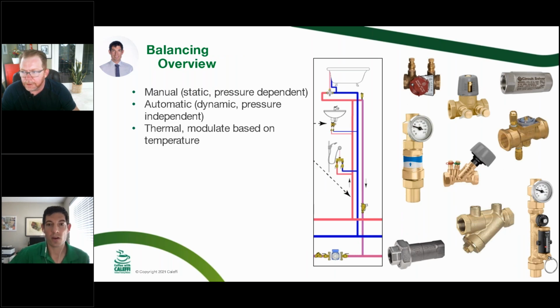Yeah. Okay, so we've got a lot of different balancing valves on the market, some from Caleffi, some from other manufacturers. Manual, where you've got a Venturi and you're just adjusting that. You've got your charts out, you've got your upstream, downstream with the Venturi effect, and you're matching up whatever your desired flow rate is with the flow chart. So static, pressure dependent. Automatic would be something like the FlowCal, which is the vertical blue valve in the center with the temperature gauge. You're going to pick a cartridge with the GPM that you desire, and within reason, there's a minimum and a maximum GPM, it's going to keep that flow rate where you want it, because there's a cartridge with a different flow pattern that's going to come in and out with the spring to make sure that you've got the 4.2 GPM, whatever you pick.